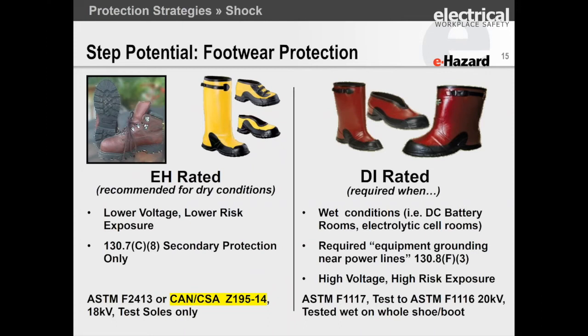Every electrician should be wearing an EH-rated shoe and put on a DI-rated overshoe if they absolutely need that. And there are certain situations where the DI shoes are better or would be needed because they're actually rated all the way up the boot to 1 inch from the top, whereas an EH shoe's only rated on the sole, but they are rated at 18,000 volts and they're tested, but they're tested on the soles only. They are considered low voltage shoes, EH is. DI is considered a medium voltage shoe.